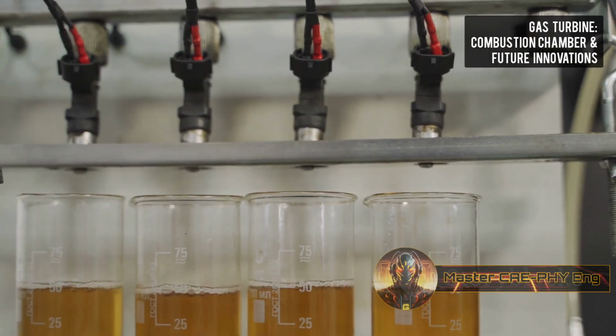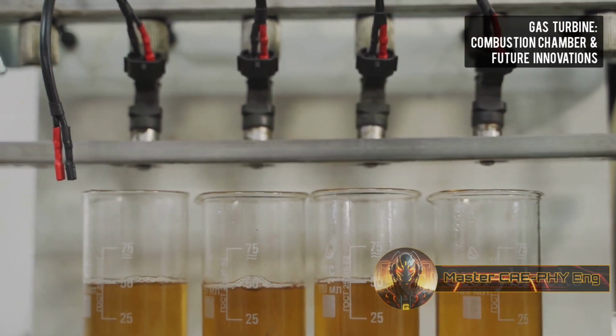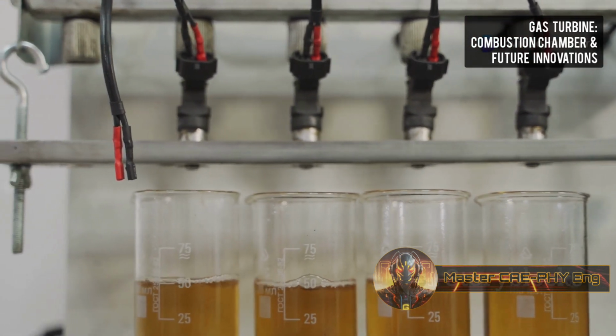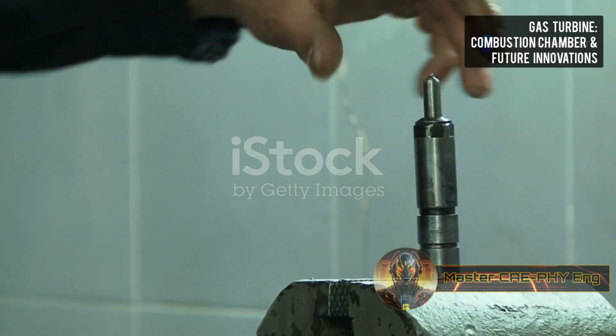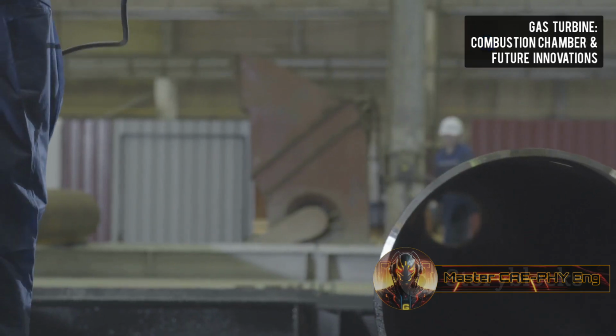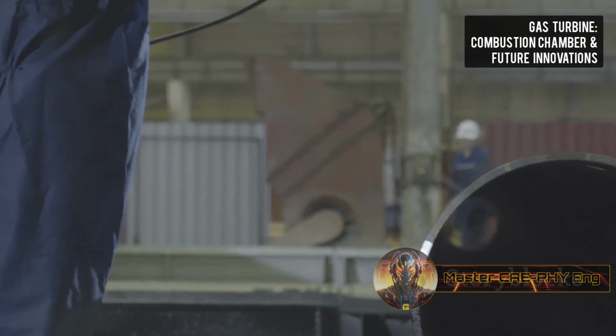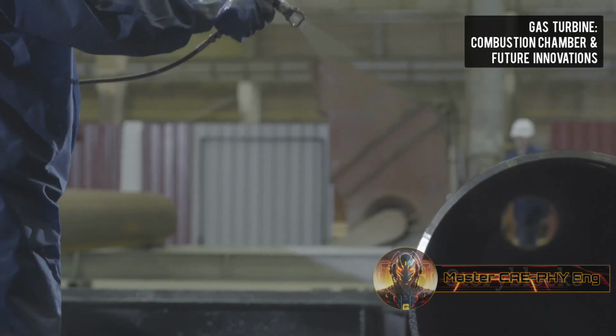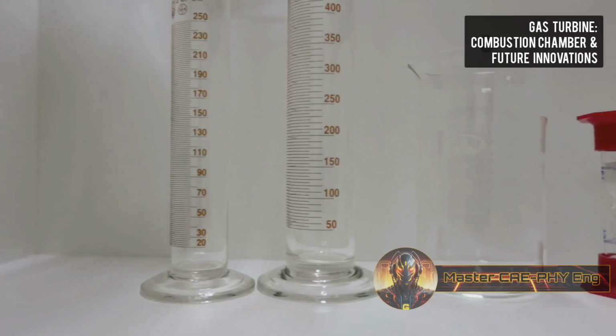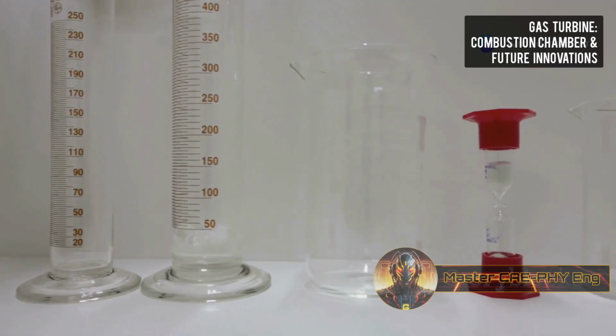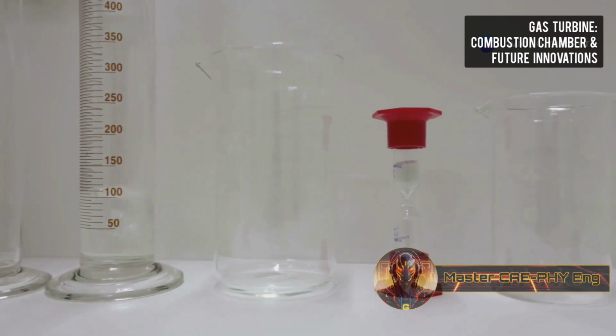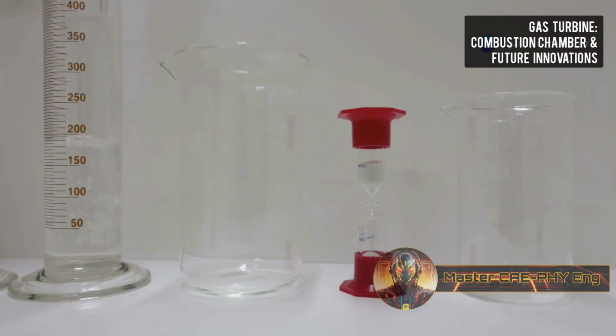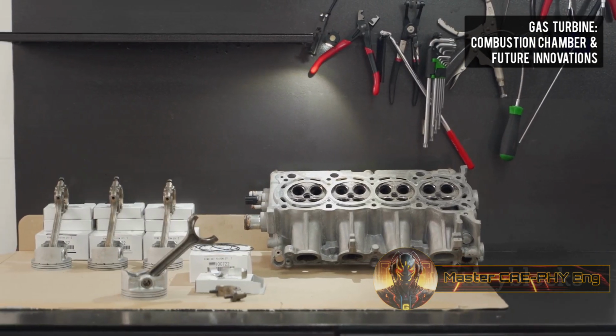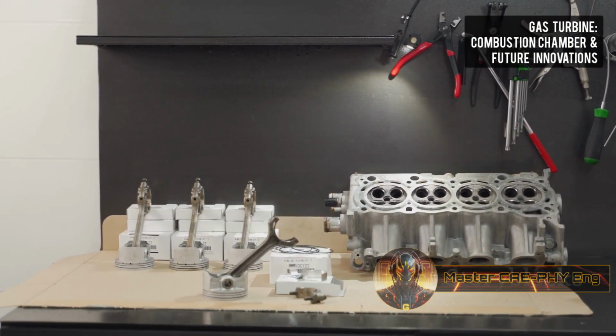Fuel injection systems are critical for delivering the fuel to the combustion zone in the correct state and distribution. For liquid fuels, atomizers are employed. Common types include pressure atomizers, air assist atomizers, and air blast atomizers. The quality of atomization, characterized by droplet size distribution, directly affects combustion efficiency, ignition, and emissions. The strategy for fuel injection also depends on the combustion concept being employed.